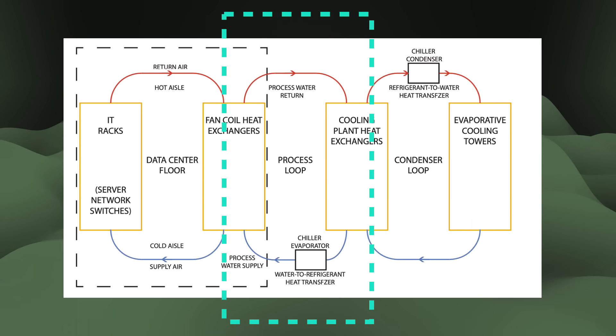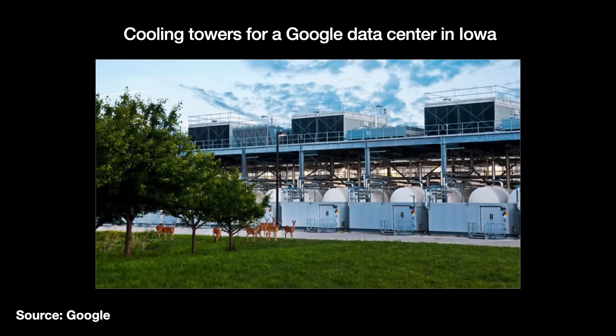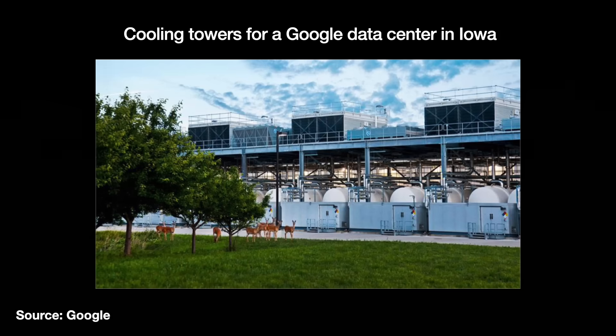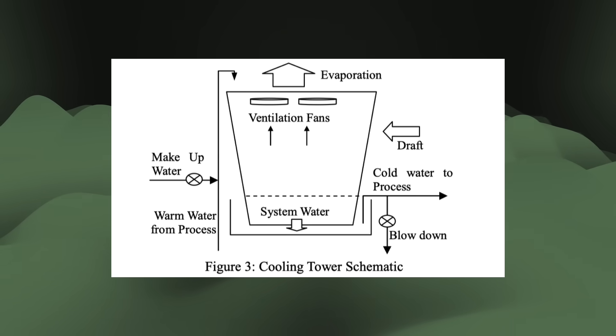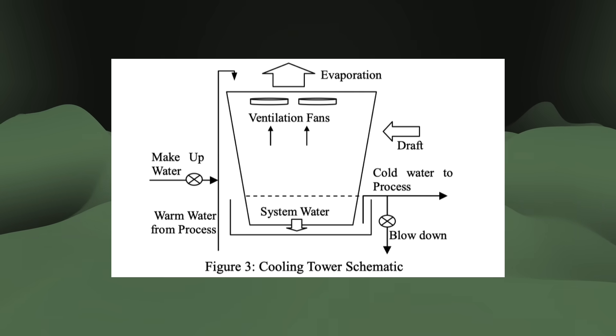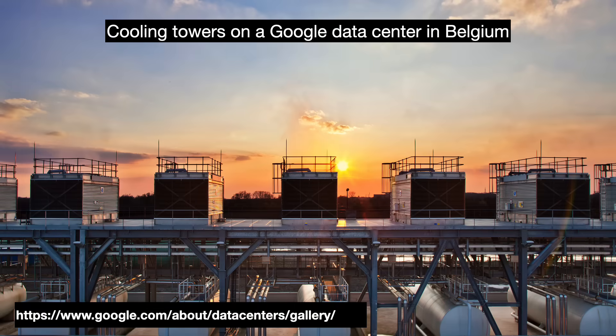In the process loop, heat is taken off the data room floor by a fluid refrigerant, usually a mix of water and glycol, then transferred to the water-based condenser loop for final transfer outside. This two-loop system is reminiscent of nuclear power plants and prevents contamination between inside and outside, granting greater operating flexibility and efficiency. At the end, cooling towers cool the water in the final loop — hot water flows down, some evaporates releasing energy, and cooled water returns for reuse. About 1% of water evaporates for every 10 degrees Fahrenheit of cooling, depending on ambient conditions. Evaporated water must be replaced with new makeup water.